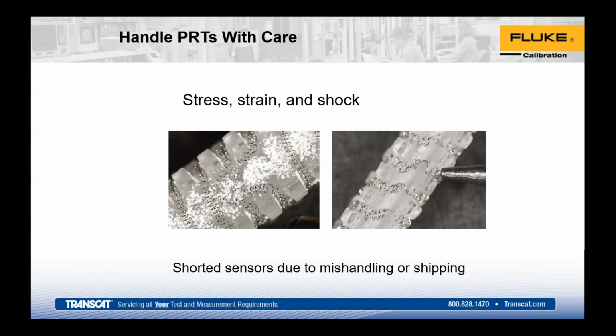So this is a close-up of an SPRT showing what shorted or strained sensors can potentially look like. We did this on an SPRT model, so these are really zoomed in. You can see the different little coils, but with shock or vibration, it can dislodge the coils or cause them to touch, which causes your resistance values to go up. Those ones really took some hits. You can see where they've touched, or this one actually dislodged from its winding groove on the far left.